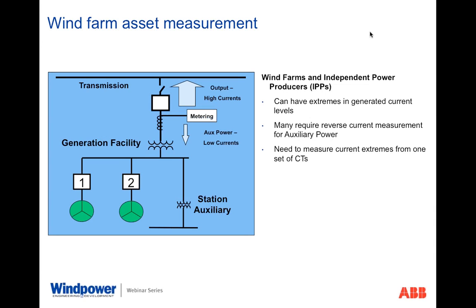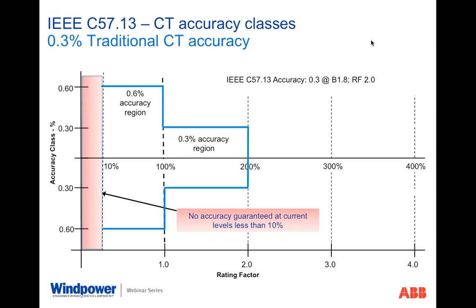So those wide swings of current, going back 12, 13 years ago, we didn't, as an industry, really know how to address the need to meter that range accurately. So we really had to look at specialized devices at that time to help address the need. So when you look at the typical 0.3 class transformer, which at that moment in time, 12 years ago, was all we had tool-wise to take to this application, it had limitations. 0.3% accurate was acceptable for normal metering installations where you stayed within a given range of current level measurement.